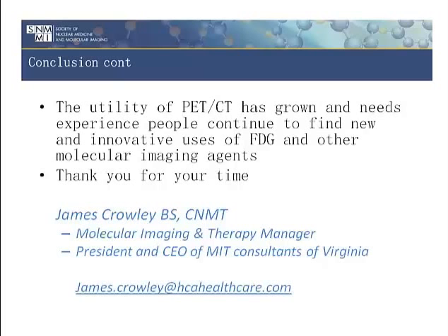We're doing it now. We're testing it. What we're doing is you do the scout scan, you do the CT scan, and then you hit the button to start the PET before you do the injection. And then since you acquire it in list mode, you could rebin it by the second, by the 2 second, by the 3 second.